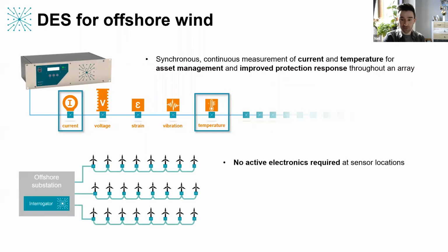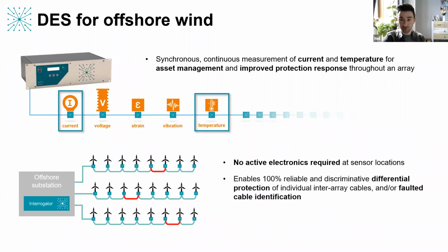So if we just have a look at how we might deploy in a typical offshore array, we could imagine installing current and temperature in the transition piece of every turbine on each string. And that would be at the cable termination points inside those transition pieces. Again, they're completely passive, so there's no active electronics required at those locations, reducing the size of that instrumentation and the amount of work that has to go into installing it. If we look first at current sensors in each of those transition pieces at the termination point, they would enable completely reliable and discriminative differential protection of the inter-array cables. And if there's already a protection system there protecting that array, then instead it would give you immediate faulted cable identification to improve the O&M response to a fault.